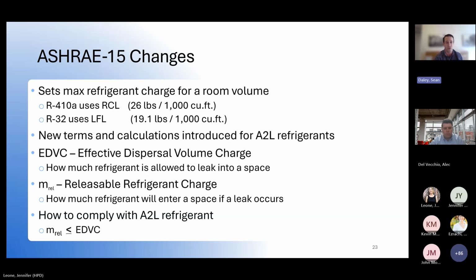Now, moving to R32, that's an A2L refrigerant. So they're not going to look at the RCL. It's much lower than R410A. They're looking at LFL, ASHRAE 15 for compliance. So that's 19.1 pounds per 1,000 cubic feet. So we're a little bit less than R410A, not crazy less, but we can't have quite as much refrigerant in a given space as we used to.